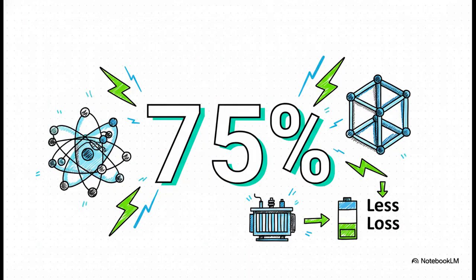And the result of that one simple change at the atomic level is staggering. Amorphous transformers can slash the main type of no-load loss, called iron loss, by up to 75%. That's a huge energy saving, all from just scrambling the atoms in the metal.